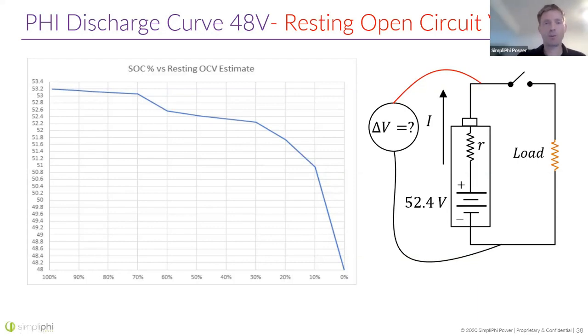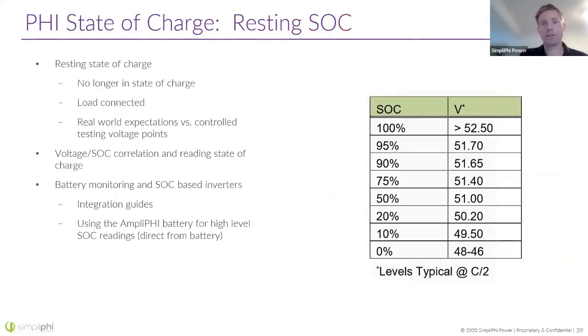There's a low battery cutout point you can set in your inverter to turn off once your battery hits this low value. If you want your battery to last longer, you use a higher low battery cutout value. We typically recommend using a 20% state of charge.